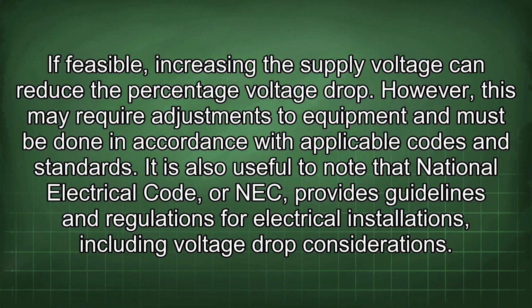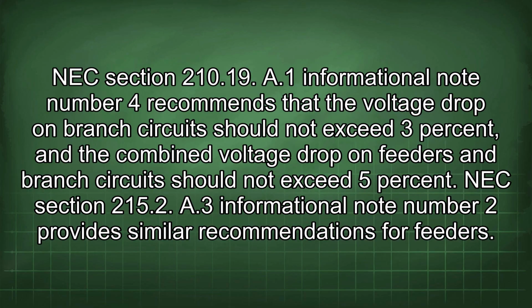It is also useful to note that the National Electrical Code, or NEC, provides guidelines and regulations for electrical installations, including voltage drop considerations. NEC Section 210.19(A)(1) Informational Note Number 4 recommends that the voltage drop on branch circuits should not exceed 3%, and the combined voltage drop on feeders and branch circuits should not exceed 5%. NEC Section 215.2(A)(3) Informational Note Number 2 provides similar recommendations for feeders.